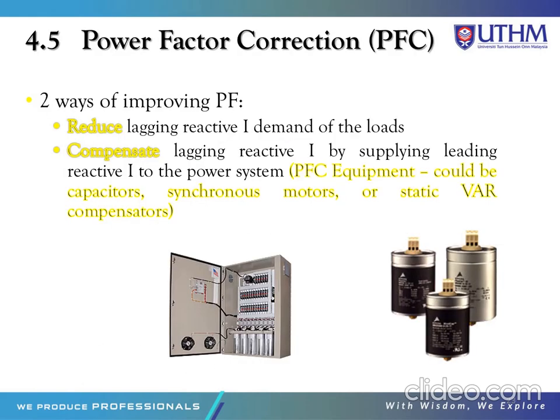Next we go to subtopic 4.5, power factor correction. After we know what power factor is and how to measure it, we have to know how to improve it. There are two ways of improving PF. The first is to reduce the lagging reactive current demand of the loads. As I showed in the previous slide, when the lagging is more, the power factor is lower. The second is to compensate lagging reactive current by supplying leading reactive current to the power system. PFC equipment could be capacitors, synchronous motors, or static var compensators.